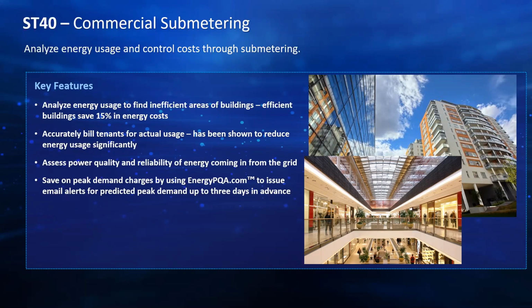Also with peak demand charges, you could, in addition to monitoring tenants, allow them to view their peak demand. So if they are getting close to what their peak demand is, they can take moves to lower that peak demand. This is a way that us as utility customers can work with the utility to lower utility demand requirements.